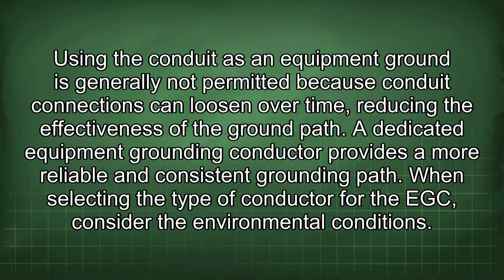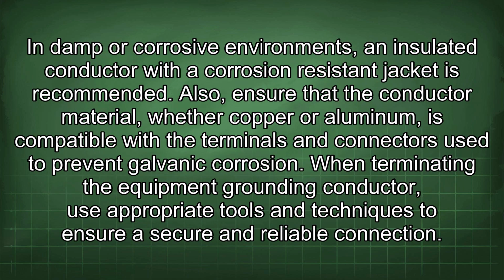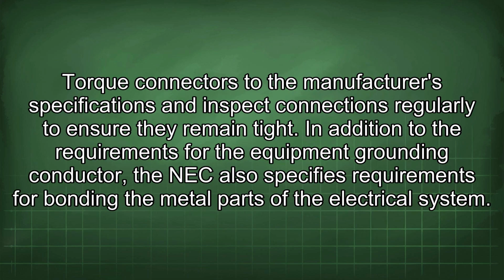Using the conduit as an equipment ground is generally not permitted because conduit connections can loosen over time, reducing the effectiveness of the ground path. A dedicated equipment grounding conductor provides a more reliable and consistent grounding path. When selecting the type of conductor for the EGC, consider the environmental conditions. In damp or corrosive environments, an insulated conductor with a corrosion-resistant jacket is recommended. Also, ensure that the conductor material, whether copper or aluminum, is compatible with the terminals and connectors used to prevent galvanic corrosion. When terminating the equipment grounding conductor, use appropriate tools and techniques to ensure a secure and reliable connection. Torque connectors to the manufacturer's specifications and inspect connections regularly to ensure they remain tight.